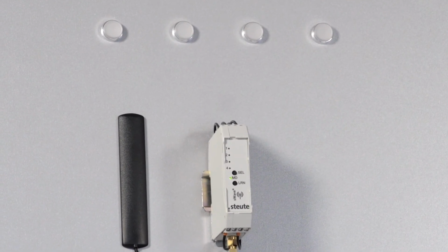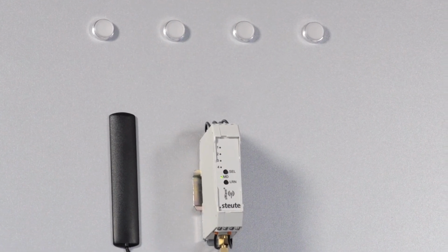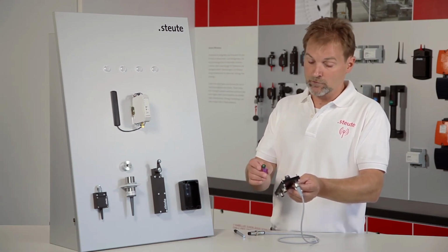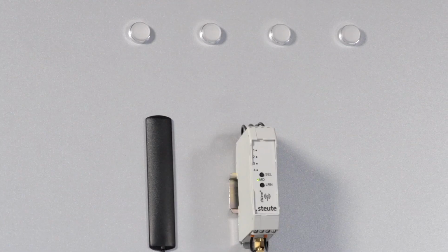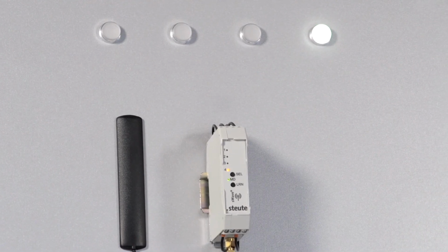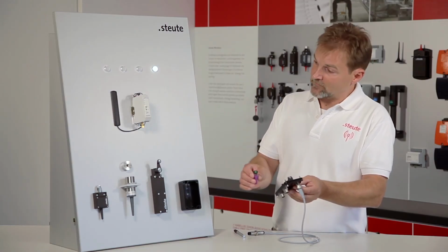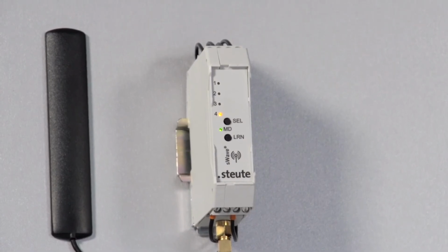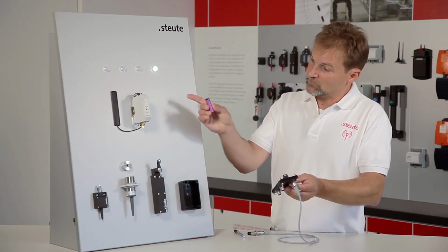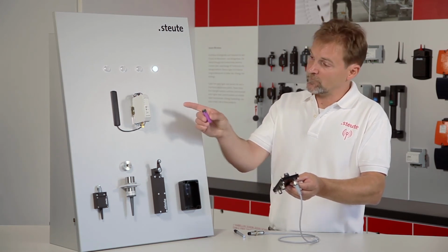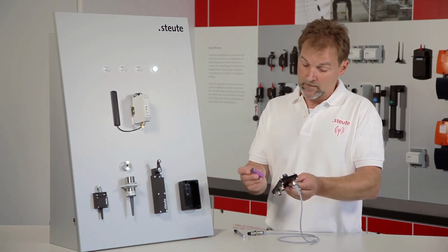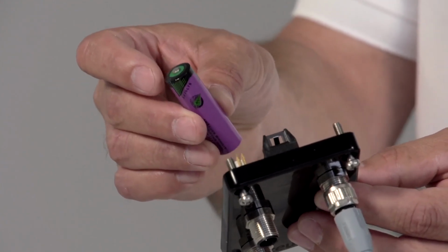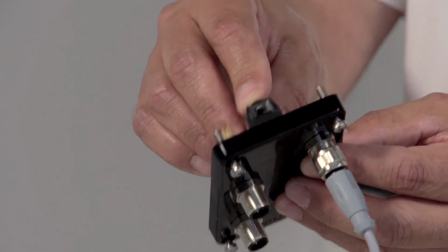I remove the battery and the interval begins. 22 seconds while the receiver waits for a status signal, which in this case does not come. After 22 seconds, LED 4 lights up to indicate this, as you can see here. Because a status signal did not come from the RFIO, the receiver waited 22 seconds and then lit up LED 4 to indicate this in the operating mode status signal monitoring. If I now replace the battery and return power to the transmitter, the status signal is sent once more and the system is back where it should be.